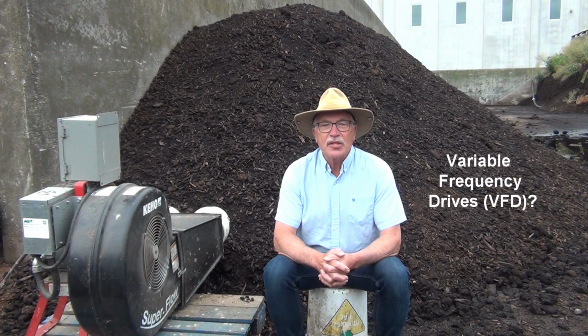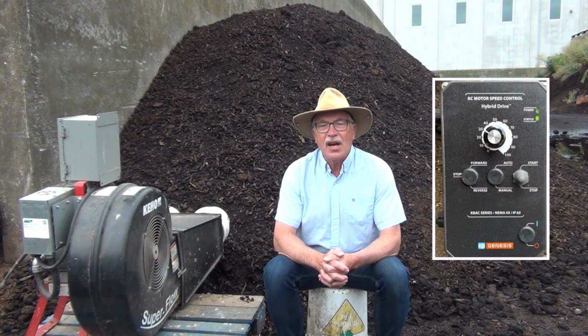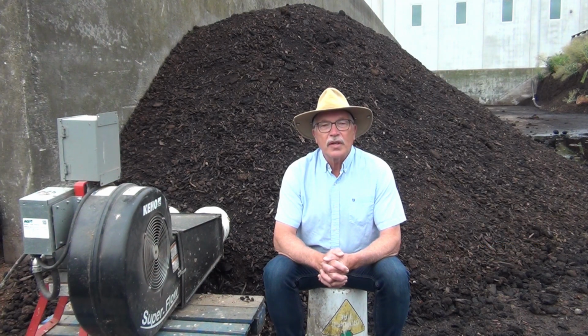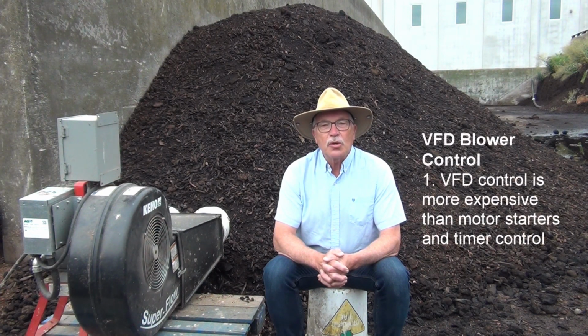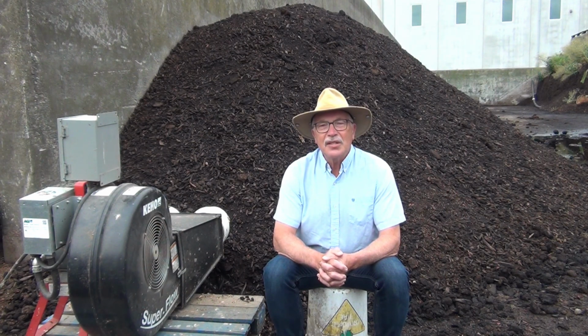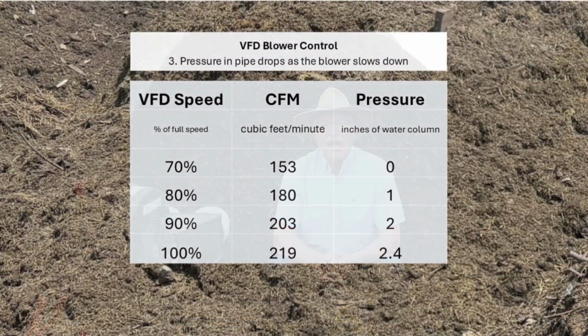I've had questions. Why don't you use variable frequency drives, otherwise known as VFDs? You can ramp up the blowers as the compost needs more air rather than the hard starts or stops. We tried this more than 20 years ago with one of our first composting projects. There are three things to think about using VFDs. First, VFD controls are much more expensive. Secondly, we've had blowers turn on and off every 30 minutes for over 15 years using simple contactors, and they're still working just fine. And third, I prefer to pressurize the air pipes to optimize air distribution.